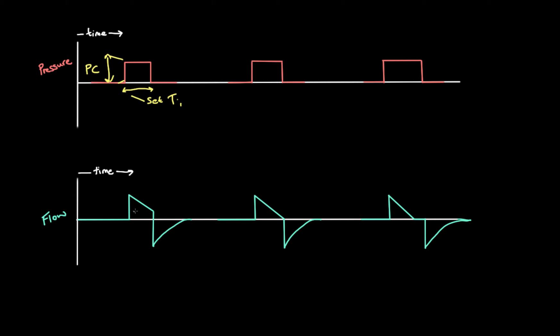We set a pressure and apply it for a certain amount of time. As a result, there's flow generated — applying pressure to the circuit causes inspiration and flow into the patient. The flow spikes up and then decelerates, giving this decaying flow pattern which is typical in pressure control. Then inspiration ends here at this sharp line. Flow returns again in the opposite pattern — it starts quickly and then decays back down to zero. Positive flow for inspiration, negative flow for expiration.